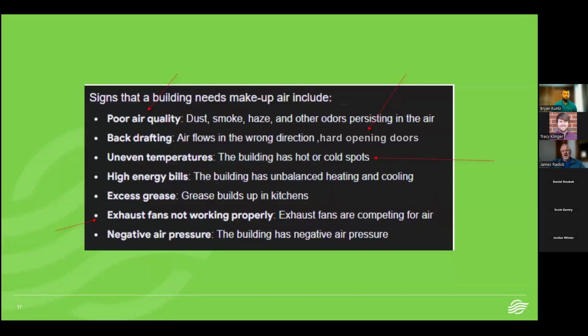Okay. And you're probably all familiar with these. Just drop that in there. Signs of building needs makeup air. There's a lot of them out there. There's poor air quality. You just can't get rid of the nasties that are inside the building because of the things we talk about: backdrafting, hard opening doors, etc., uneven temperatures.